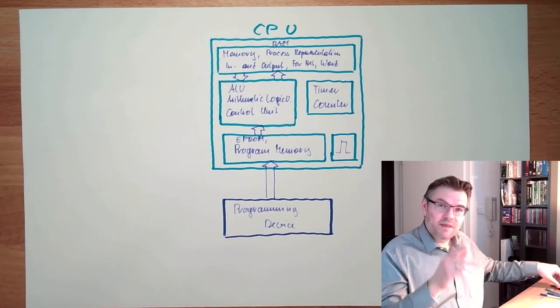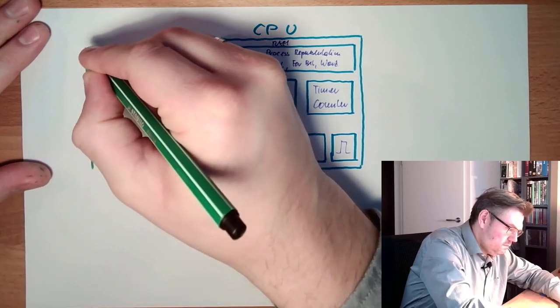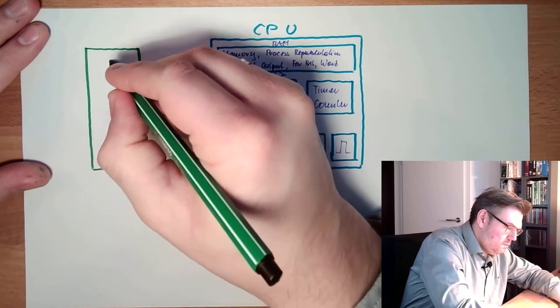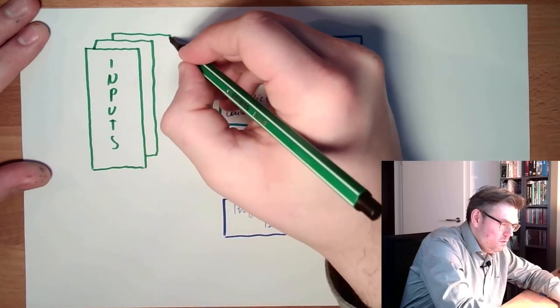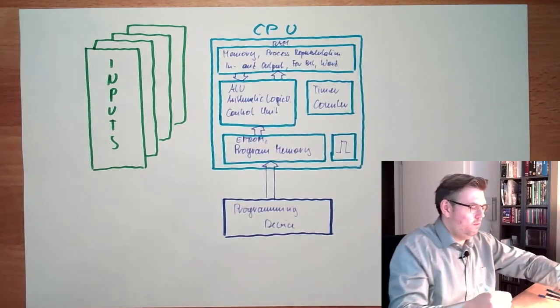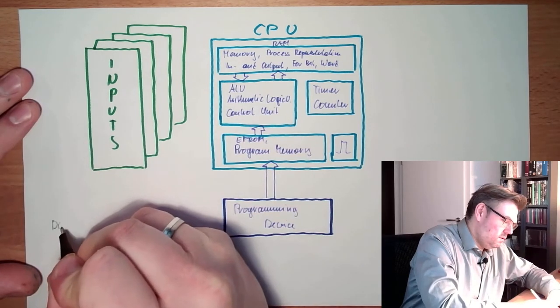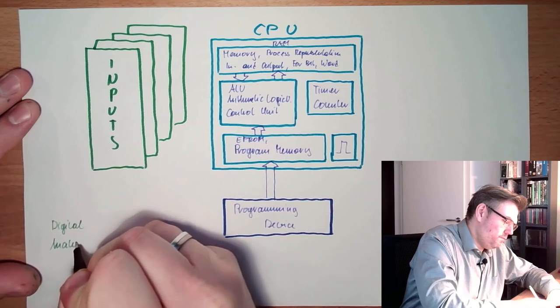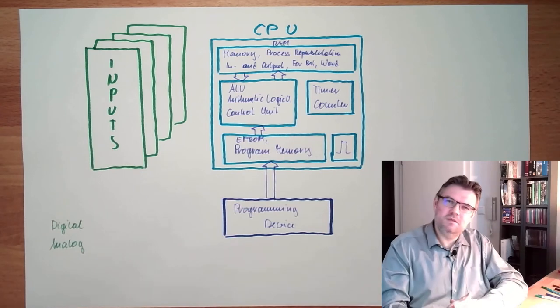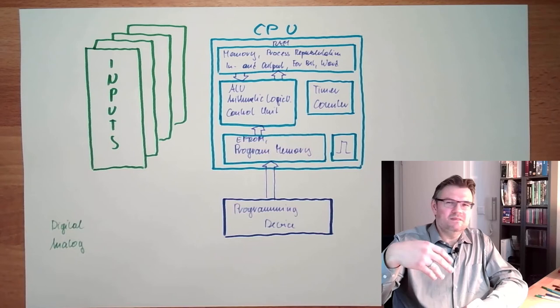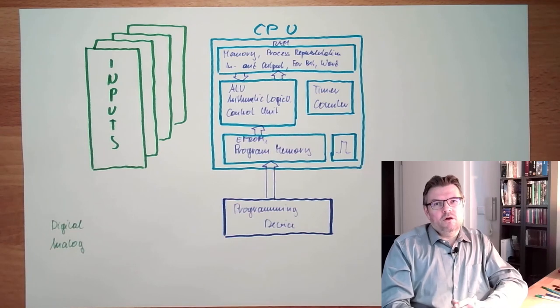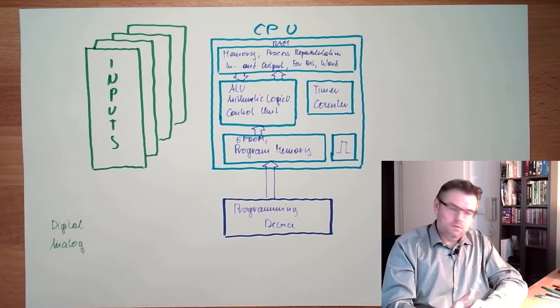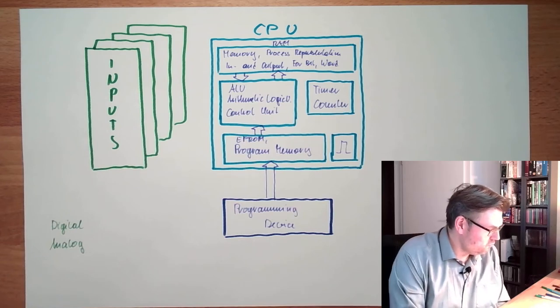Then there are inputs, input cards, not one but more, whatever. Those input cards, they might be digital or analog. Digital cards usually have a bunch of inputs, 8, 16, 32, something like that, usually in blocks of 8, and they are numbered. They are numbered according to the byte number. They have a certain address and so on.